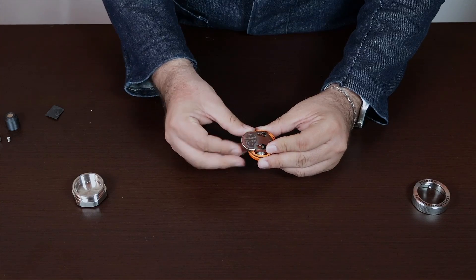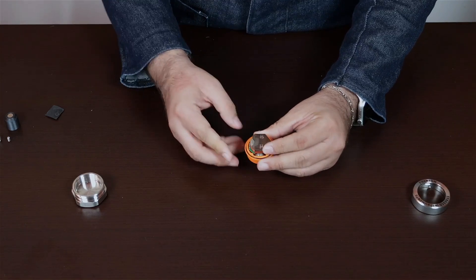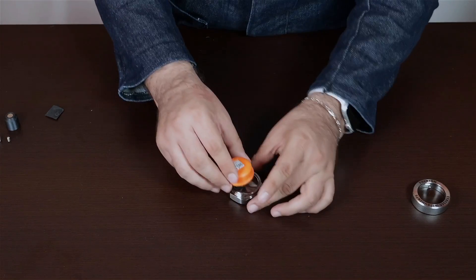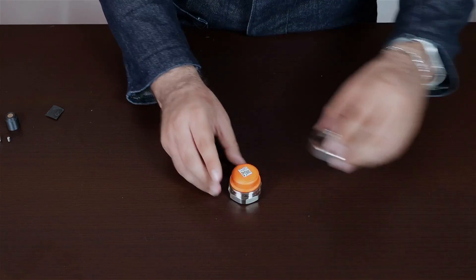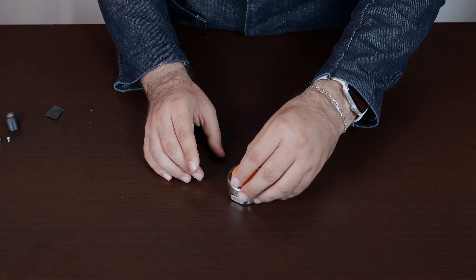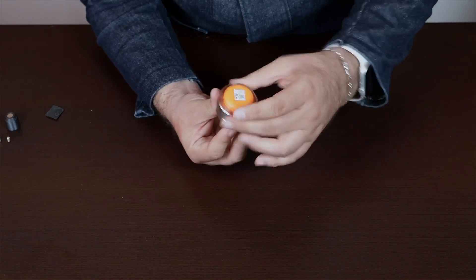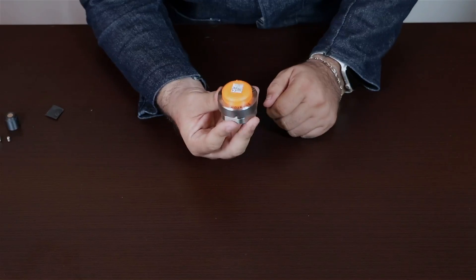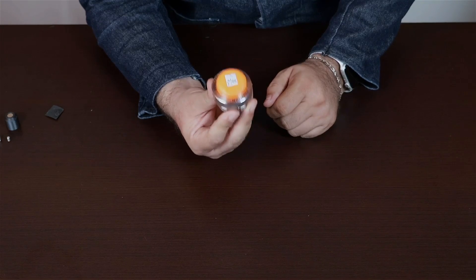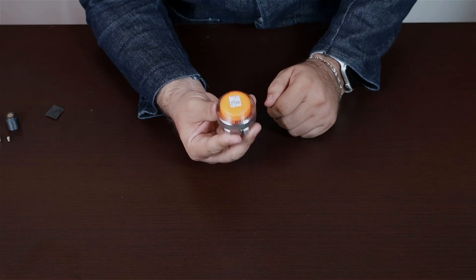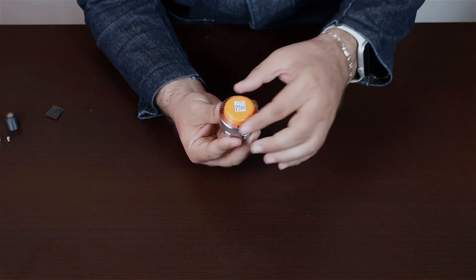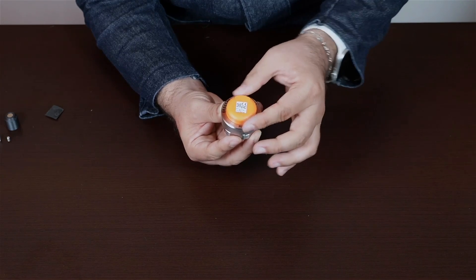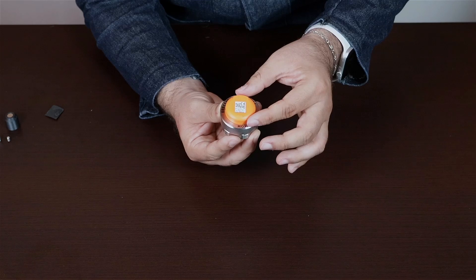When placing the new battery, you can close the sensor again by placing it on its metal base and reattaching the nut. This nut acts as a seal and repositions the base. As you can see, the plastic part remains movable, so you can orient the accelerometers as desired, and then fix the nut to keep the sensor stable with the axis pointed in the desired directions.